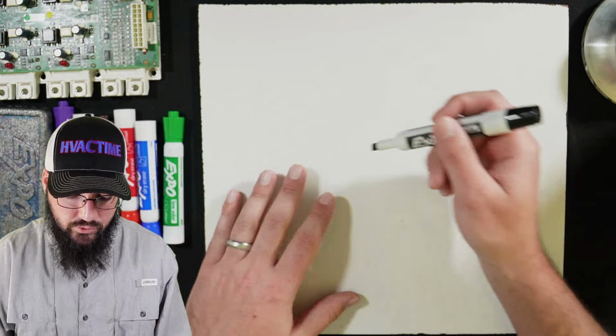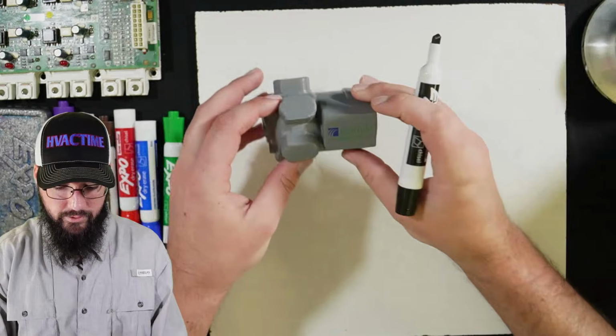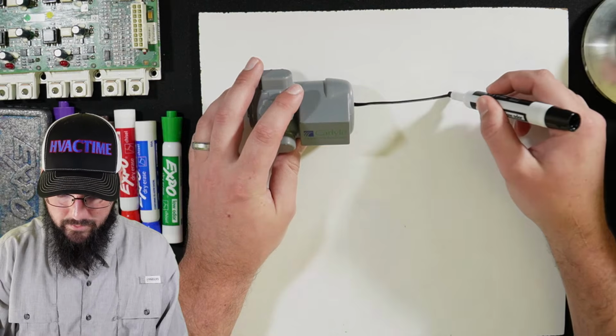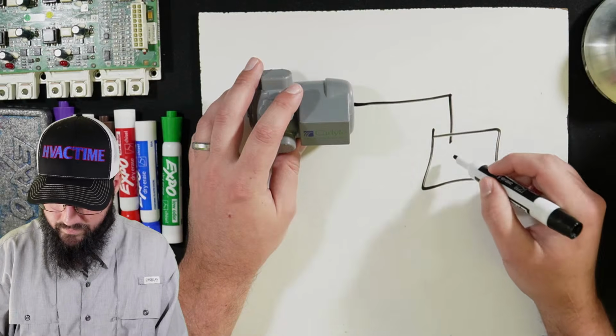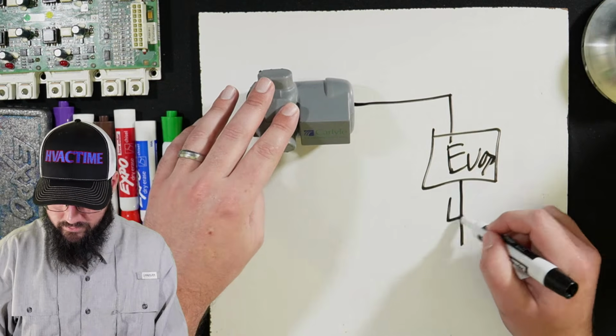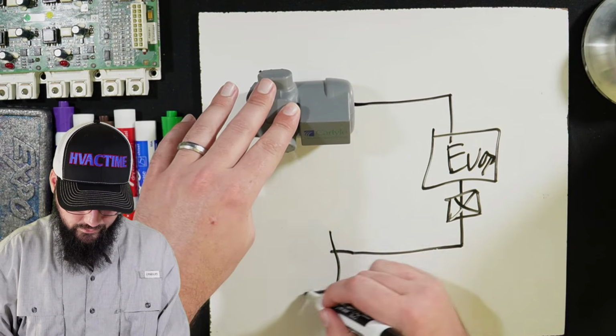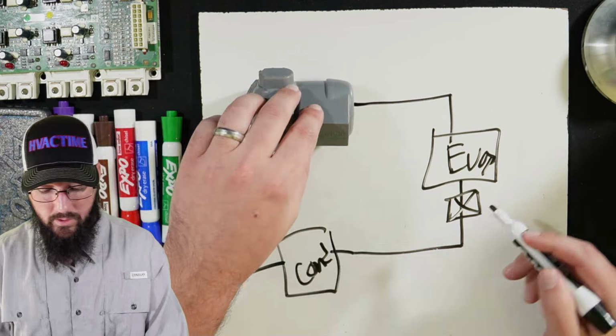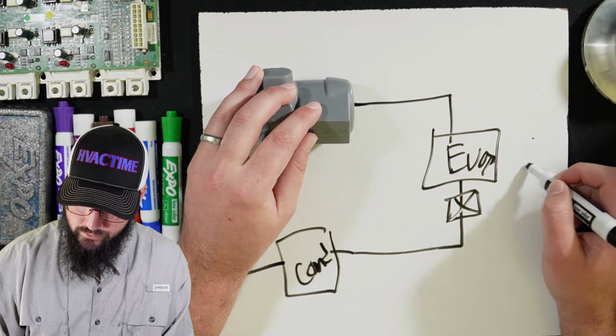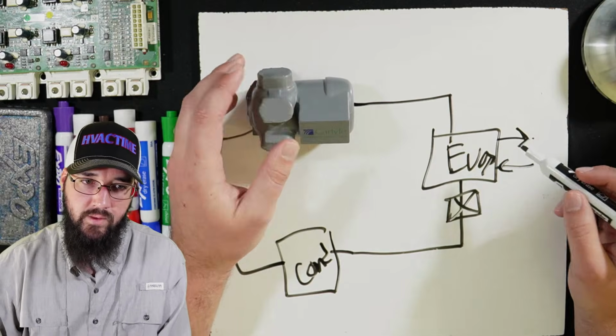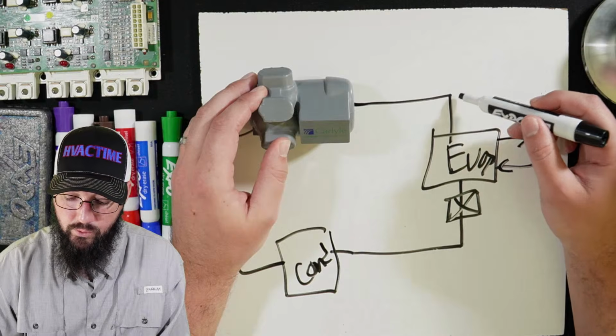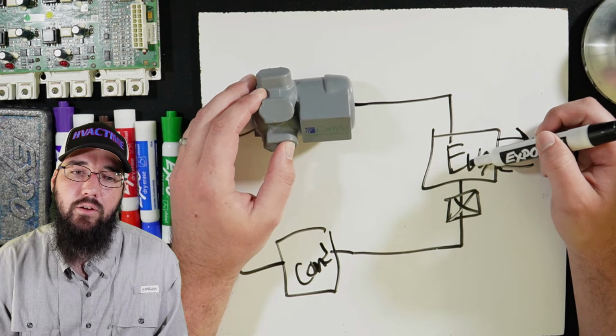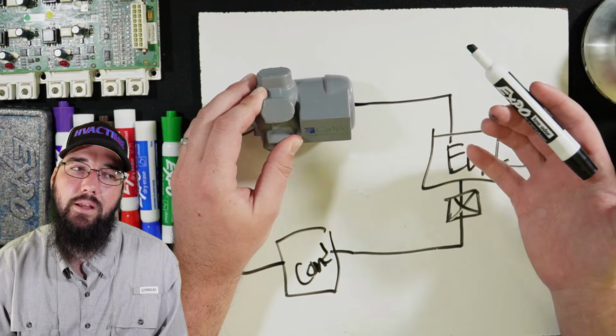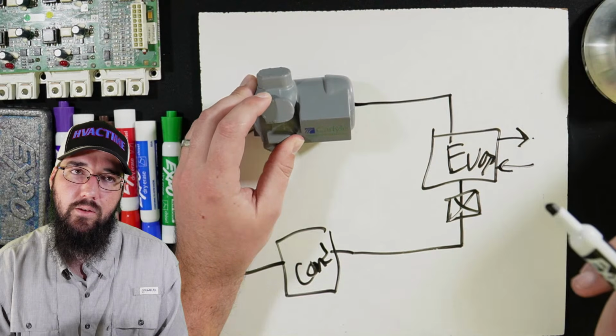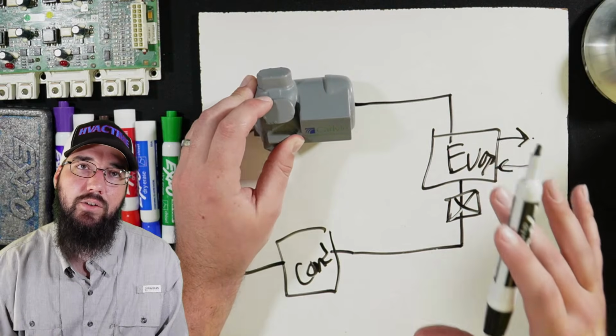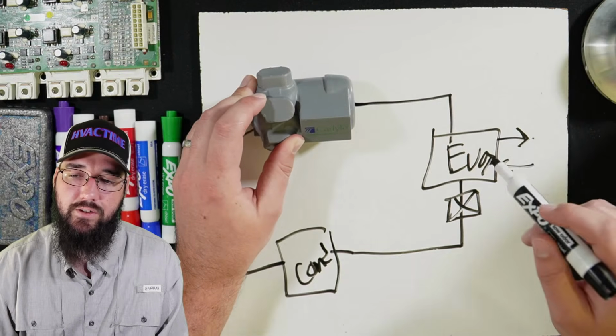Okay, so let's just draw a circuit. I think this will help visualize. We'll use an example here. We'll get our little compressor buddy. So let's just say this is our suction coming out of the evap. And then we've got our metering device and a condenser and so on. We all know a basic circuit cycle. Let's get our water. As this compressor unloads, we're moving less CFM through the evaporator. A natural result of that is we're going to increase saturation a bit. Actually, we're going to increase in comparison to where we were, but it might actually stay fairly stable.